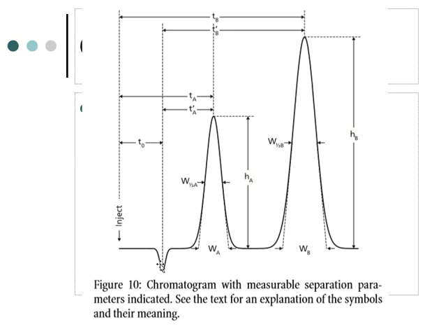Your sample is now venturing out, and it's getting into the conductivity detector, and that conductivity detector measured that disturbance a little bit, because that's almost like a water molecule that's sent through the column. It's disturbed the conductivity a little bit. It's made it plummet, go down, because pure water will read close to zero, and then it goes back up to baseline, because now it's just all mobile phase again. So this is what we would call the water dip.